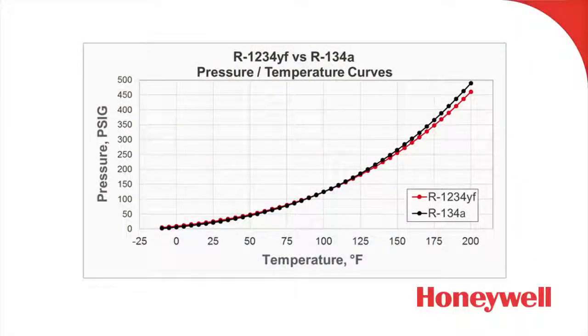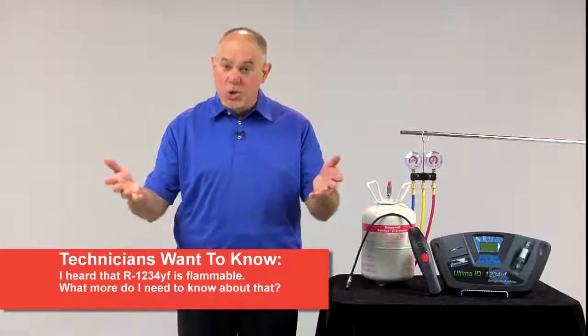As a matter of fact, here is a pressure temperature chart of R1234yf versus R134a. Taking a look at the chart, you'll notice that the curves run very much together. You can see that basically all the way down to about minus 10 degrees F, all the way up to about 150 degrees F, and that's when they start to split off a little bit. But the bottom line is you can see that the PT curves of both of these refrigerants are very, very similar to each other. So what about the flammability of R1234yf?